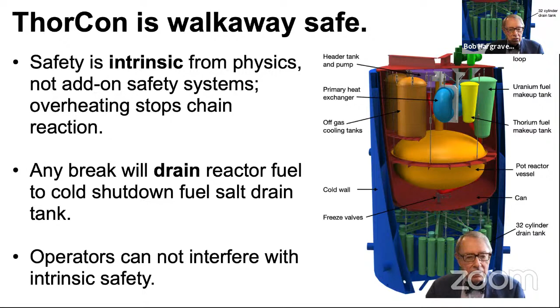A little bigger picture here. I mentioned the cooling pond that has a heat exchanger in the bottom of it, a radiator, so that we recirculate cooling water to the cold wall. The cooling pond itself is open to the air, and we can cool it for months with just that cooling water if the plant is suddenly shut down without power.